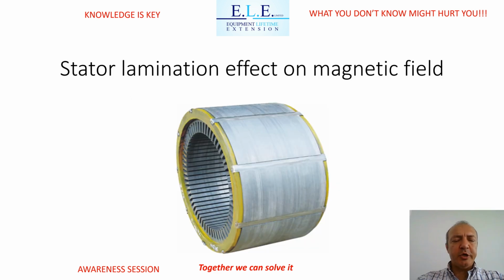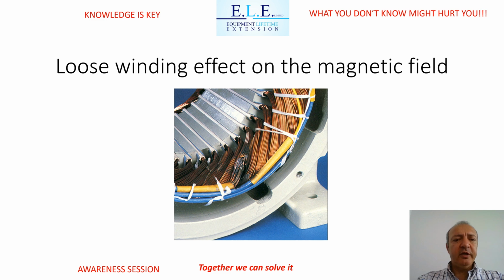Shorted stator lamination can also affect the magnetic field pulsation. Loose stator winding is another cause of magnetic field pulsation, and this can also burn the winding.